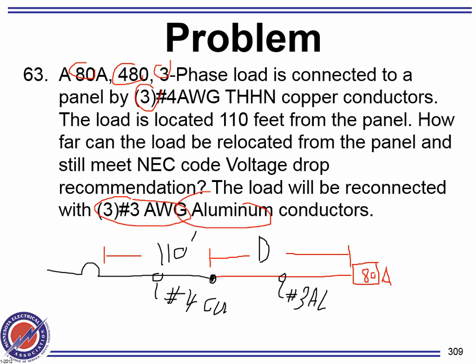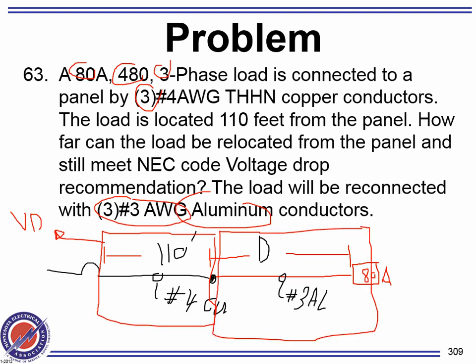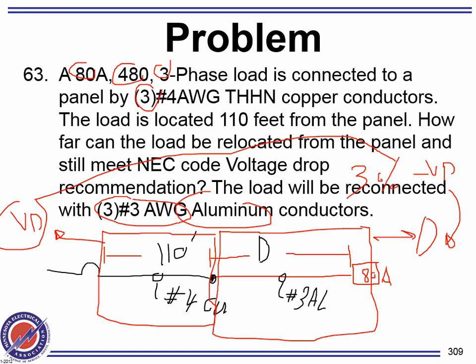Here's the first thing you need to do, guys. Do you see that section here? Look at this. From here to here, this is one problem. This is your problem number 1. Find the voltage drop right here. Once you find the voltage drop, then you start from this point all the way to this point here. You find the distance, right? Because you're going to take the voltage drop that you found here, take the 3%, subtract the voltage drop that you got, and use it as a leftover voltage drop to find the voltage drop here. Once you get the voltage drop, you know how much extra voltage drop you can lose. Gives you 2% voltage drop.